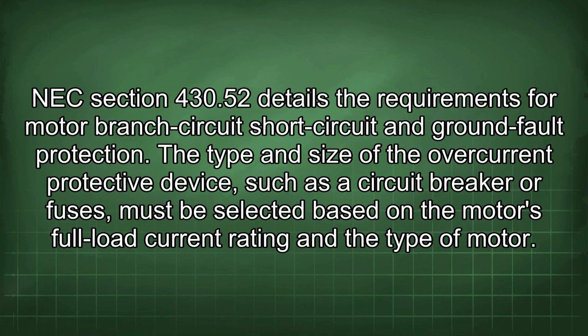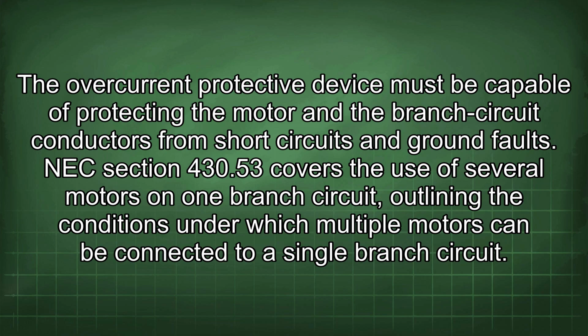NEC Section 430.52 details the requirements for motor branch circuit short circuit and ground fault protection. The type and size of the overcurrent protective device, such as a circuit breaker or fuses, must be selected based on the motor's full load current rating and the type of motor.